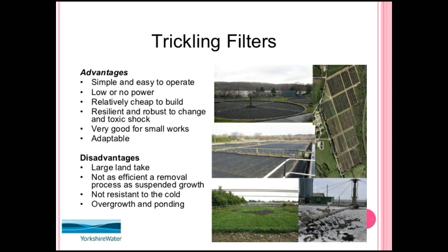Now the disadvantages. It takes up a large land area, it is not as efficient a removal process as suspended growth, it is not resistant to the cold, and it suffers from overgrowth and ponding. These are the disadvantages of the trickling filter.